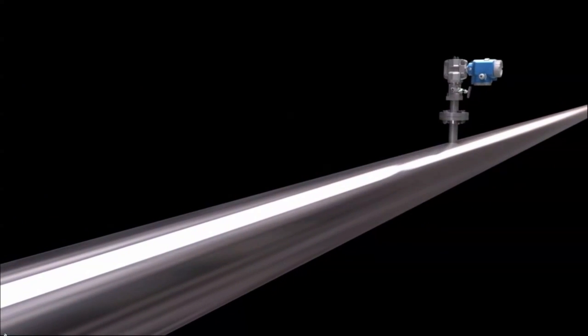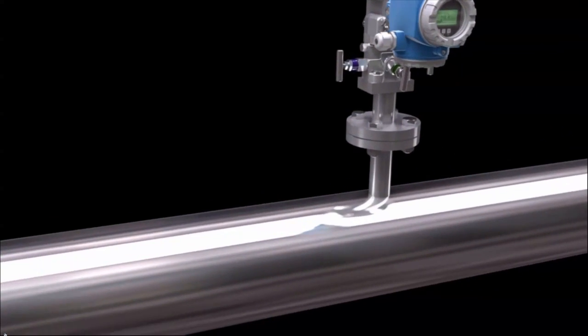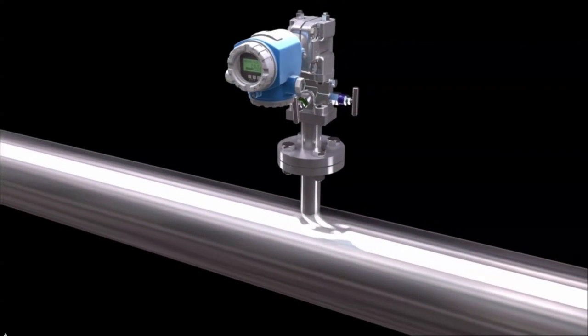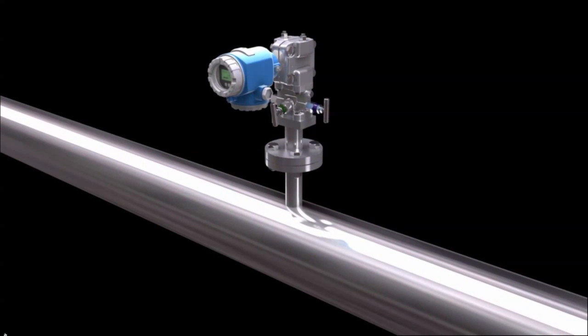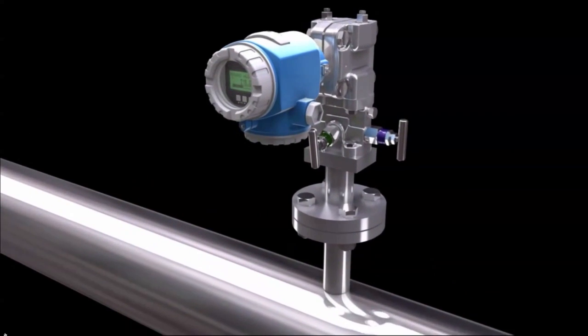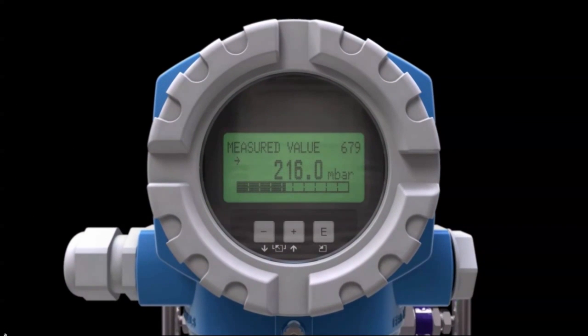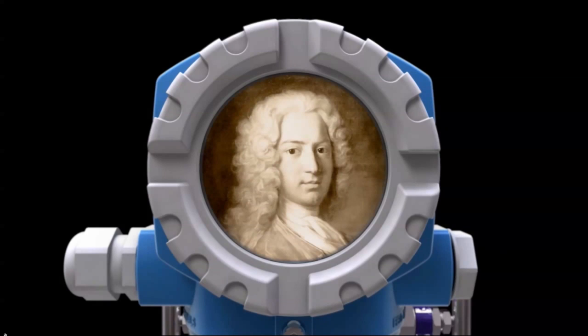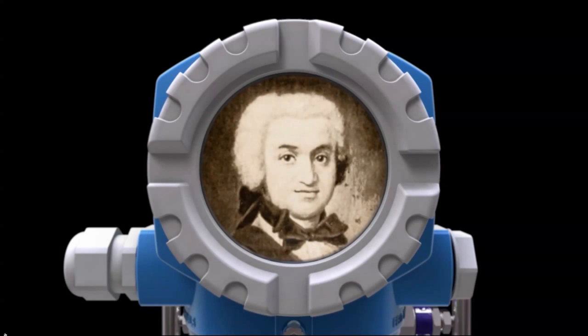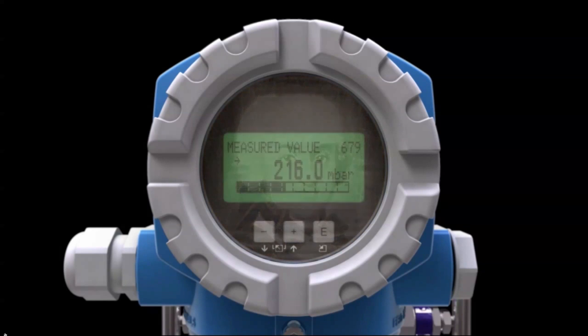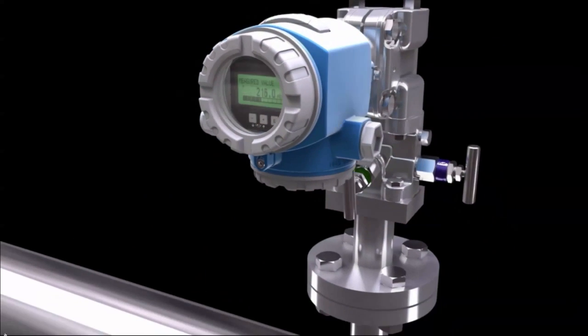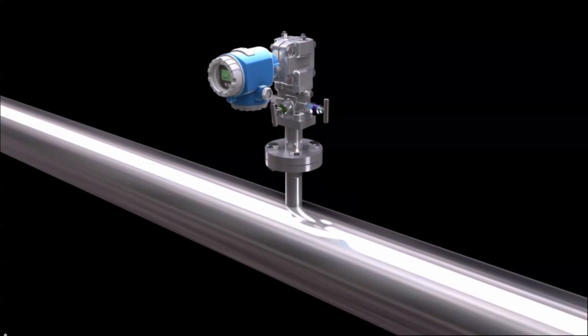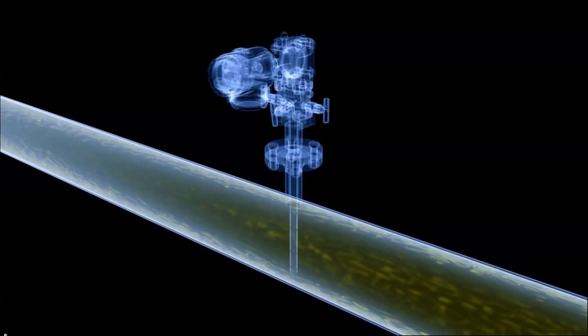One principle is flow measurement based on dynamic pressure detection using a pitot tube. Some 300 years ago, Swiss mathematician and physicist Daniel Bernoulli discovers a direct relationship between the pressure and speed of a fluid flowing in a pipe. At the same time, the French engineer Henri de Pitot is constructing a device for measuring the traveling speed of ships using flow pressure. His instrument is known as the pitot tube. Here is how this measurement method works.